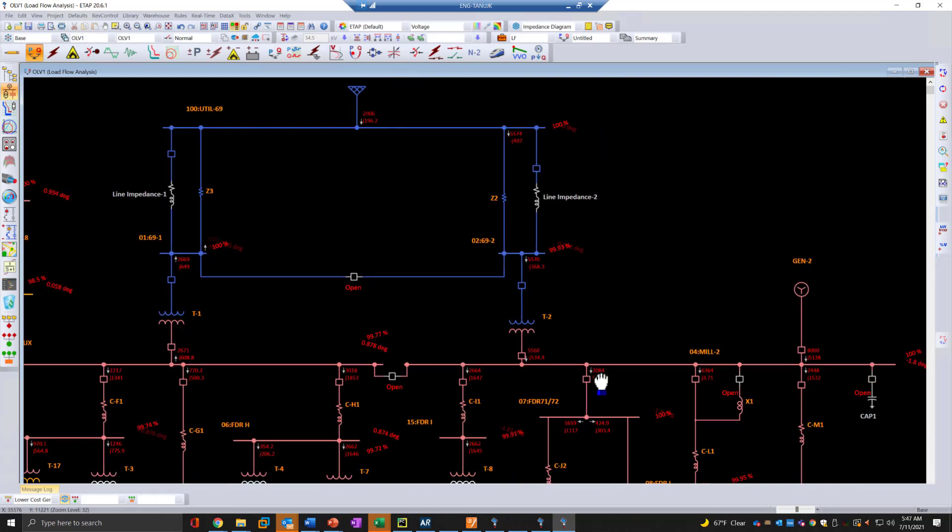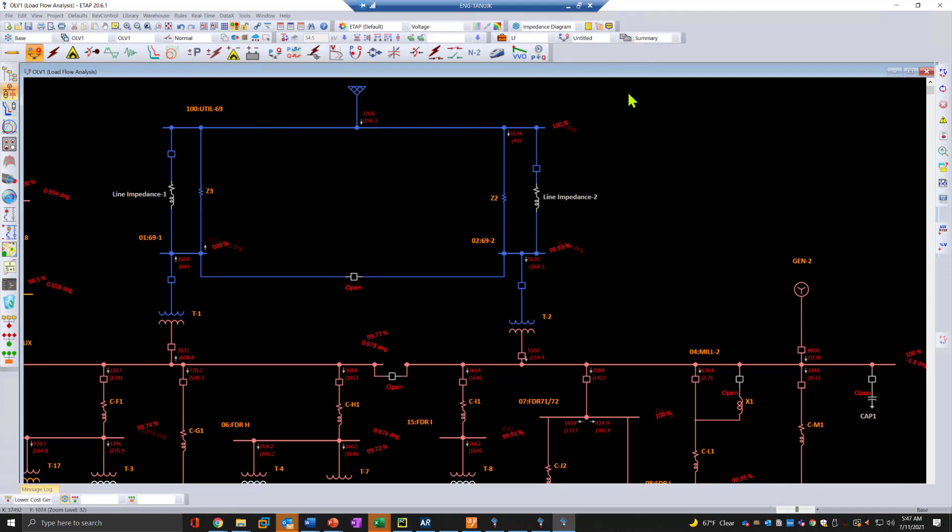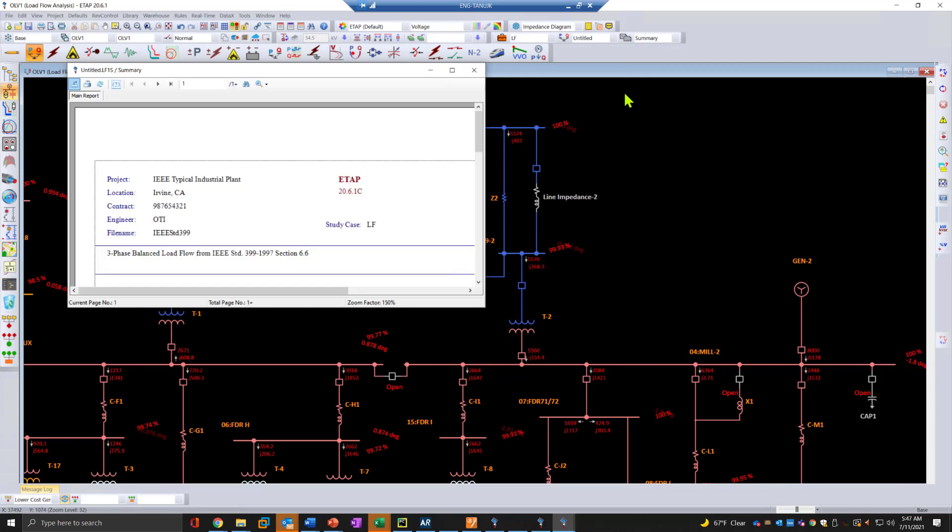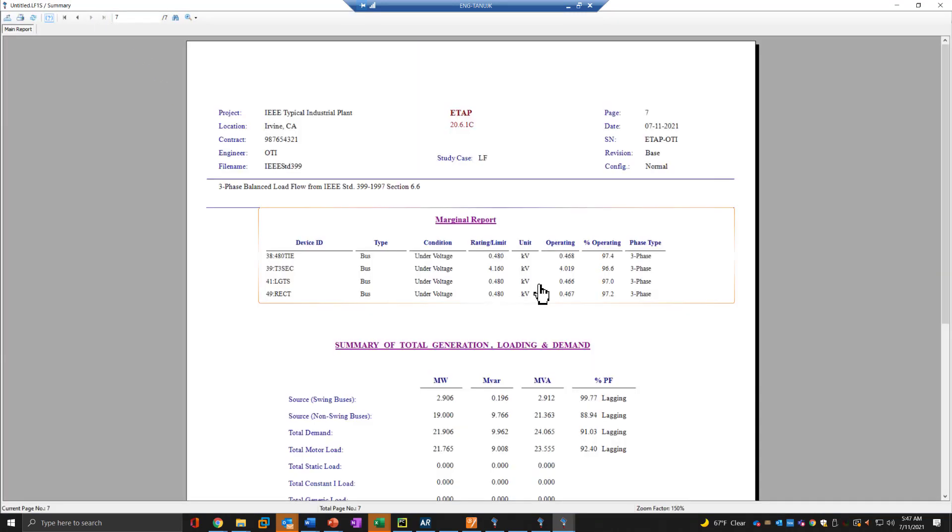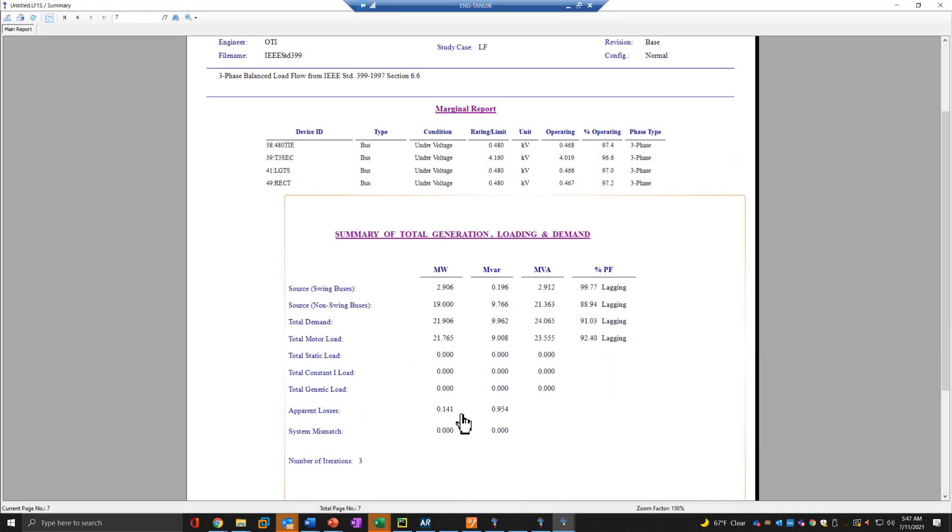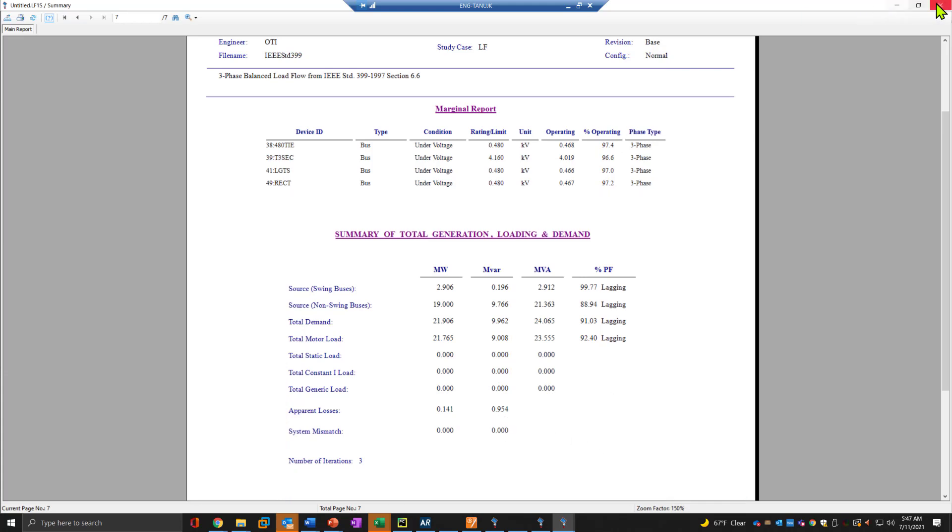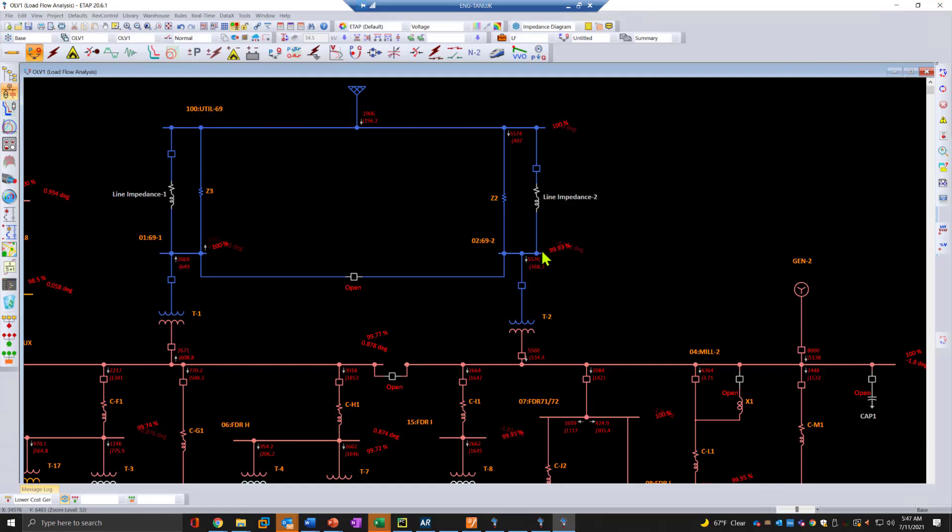About 8 megawatts from generator 2, so 11, 8, and 3 approximately. The amount of losses from this particular network can be observed inside the summary report. We can go to the last page and see that the apparent losses are about 140 kilowatt and almost 1 megavar in the system.